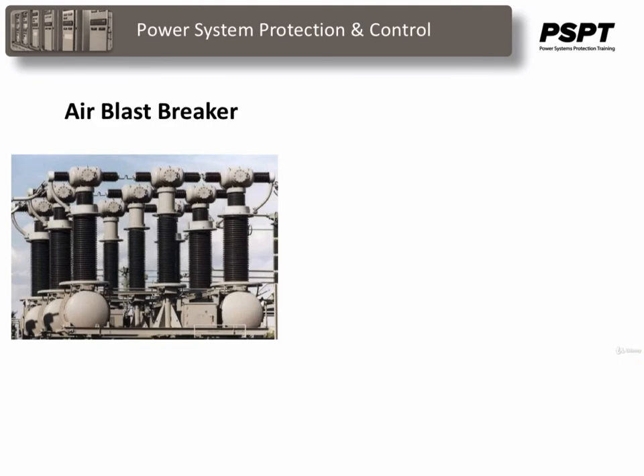Air blast breakers are, as their name suggests, just blasting away the arc produced by opening the contacts with air. This compressed air blasting across the contacts and venting into the atmosphere creates a very loud report, or a loud bang, which can be a nuisance to residential areas. So most times these breakers, because of the nature of the high voltage equipment involved, are usually located away from the general public.